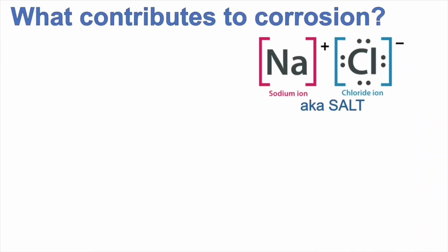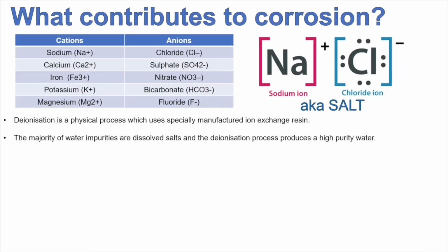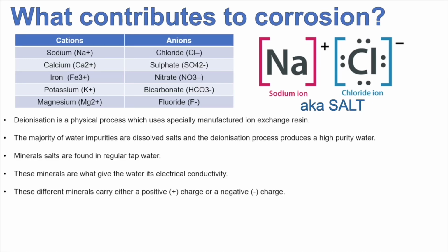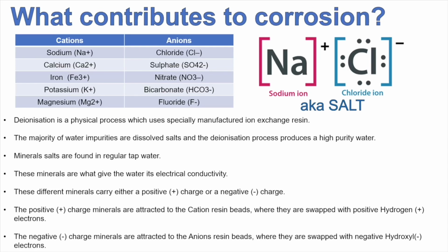Taking a look at waterside corrosion, we've got our cations and anions. These are the minerals that we will find in our water. You'll see that some are positively charged and some are negatively charged. They're all balanced. Deionization is a physical process which uses specially manufactured ion exchange resin. The majority of water impurities are dissolved salts, and the deionization process produces high purity water. Minerals and salts are found in regular tap water. These minerals are what give the water its electrical conductivity. These different minerals carry either a positive or a negative charge. The positively charged minerals are attracted to the cation resin beads, where they are swapped for positive hydrogen ions.